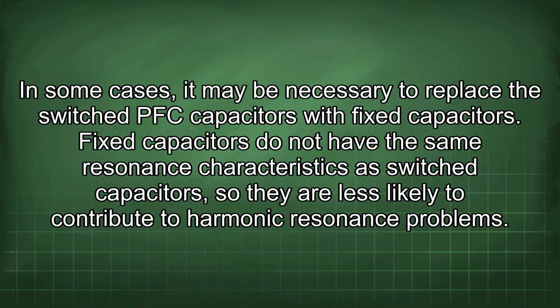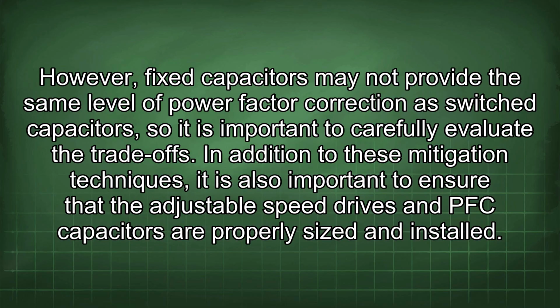In some cases, it may be necessary to replace the switched PFC capacitors with fixed capacitors. Fixed capacitors do not have the same resonance characteristics as switched capacitors, so they are less likely to contribute to harmonic resonance problems. However, fixed capacitors may not provide the same level of power factor correction as switched capacitors, so it is important to carefully evaluate the trade-offs.